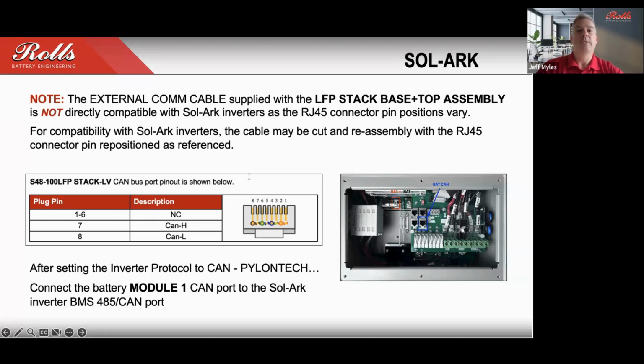Once that's connected, then you'll see visually on the Sol-Ark equipment, once closed loop communication has been established, then you'll know right away that has been set up properly because it'll be displayed on the screen. You can also verify that by looking, if you do connect the PC software and then connect to that primary battery, you'll be able to see whether or not that communication has been set as well. The information on the LFP Connect app is very convenient to be able to do directly on your phone via Bluetooth, but there's going to be some limitations in the amount of detail that's provided through the app, whereas you'll get far more detail through the PC software.